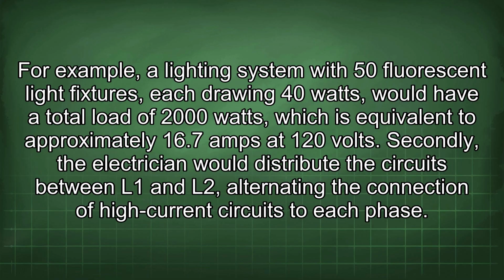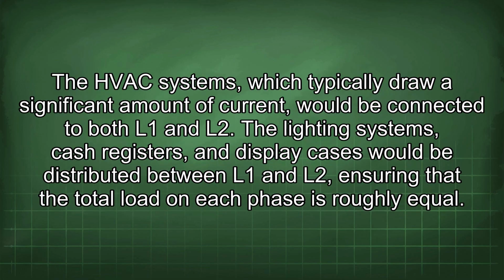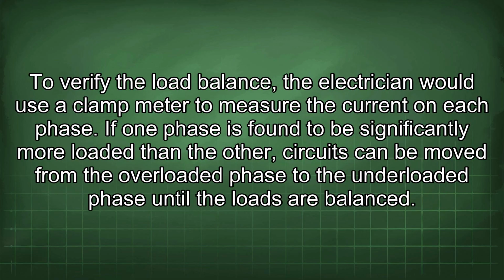Secondly, the electrician would distribute the circuits between L1 and L2, alternating the connection of high current circuits to each phase. The HVAC systems, which typically draw a significant amount of current, would be connected to both L1 and L2. The lighting systems, cash registers, and display cases would be distributed between L1 and L2, ensuring that the total load on each phase is roughly equal. To verify the load balance, the electrician would use a clamp meter to measure the current on each phase. If one phase is found to be significantly more loaded than the other, circuits can be moved from the overloaded phase to the underloaded phase until the loads are balanced.